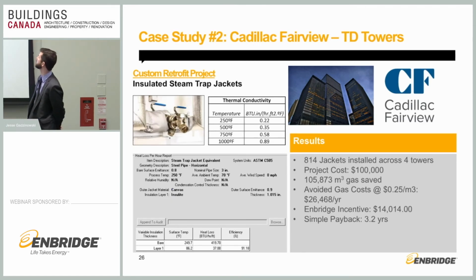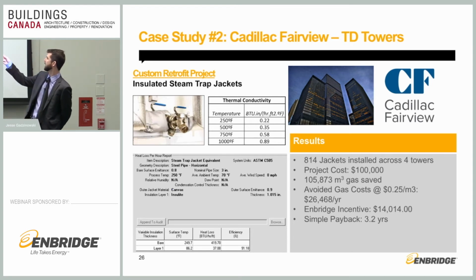This one was on the steam trap jackets. So not a lot of people are familiar with these. Some operators are and some owners, but Cadillac Fairview went ahead last year and did all of the TD towers for all of their steam systems. And they basically were interested because they have over 500 traps in the building. And if you multiply out the losses, it was substantial. Sorry, I said over 500.